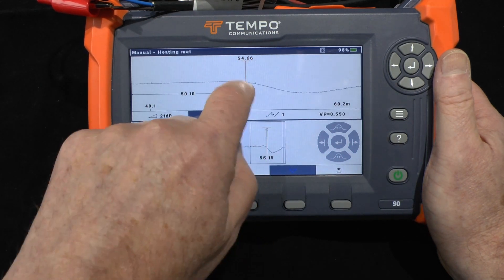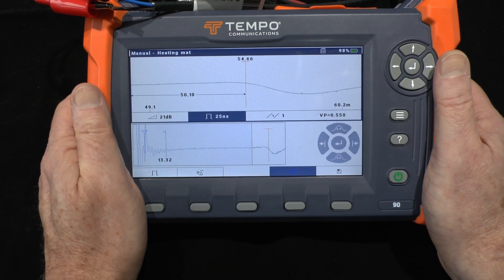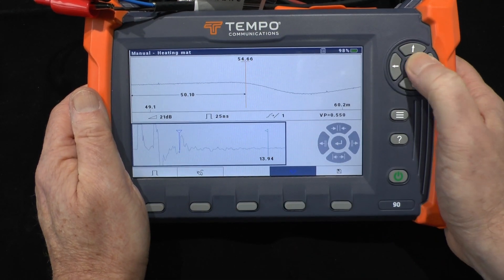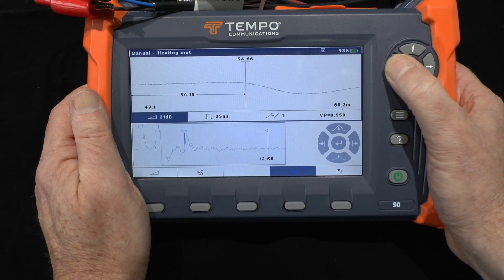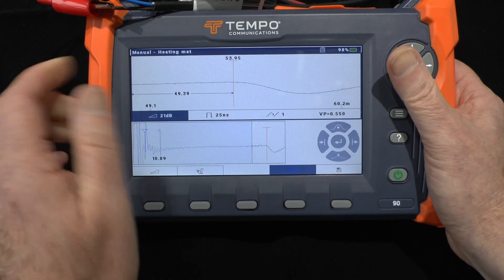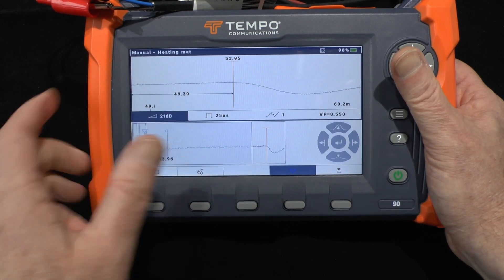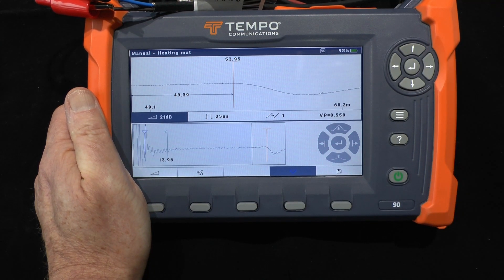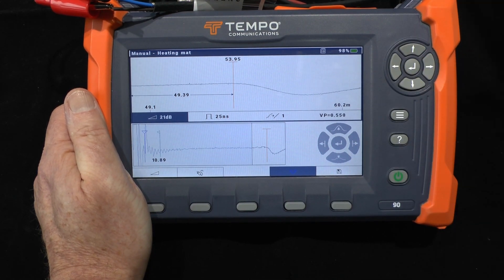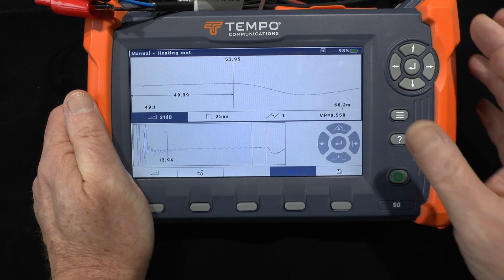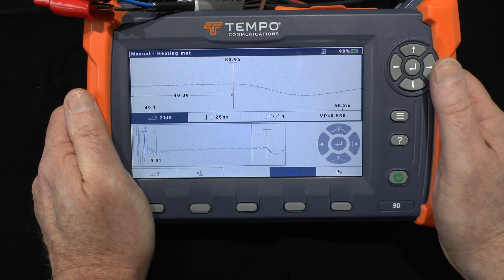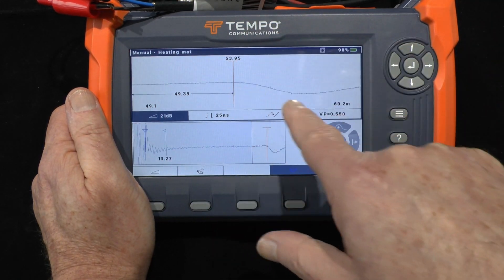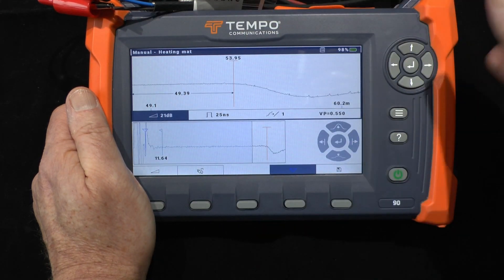Now we can see the same pulse zoomed in on the upper trace. I'll move the cursor back slightly to find the start — that measures 49.4 meters, which ties up very well with my calculations. I've got a four-square-meter mat approximately half a meter wide, and I calculated the cable to be about 49.1 meters, so this VP is approximately right. This is showing me the shorted end of the two wires within the heating cable where it loops back — everything checks out.